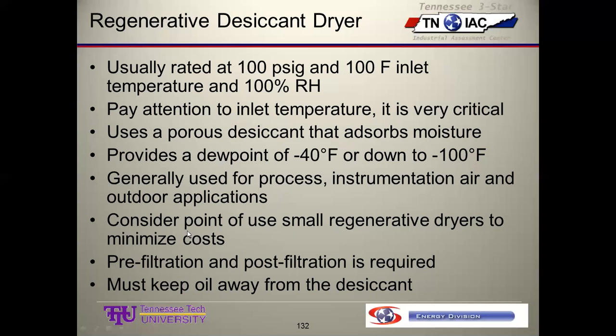One possibility, instead of drying all of your compressed air to this low a dew point, would be to generally dry with a refrigerated dryer that would get us a 35 to 38 dew point, and then put some small desiccant dryers at a particular application that might need drier air, and not dry the entire compressed air stream to this low a dew point. Something that can be considered. They make the real small ones as well as large ones, so that can work.